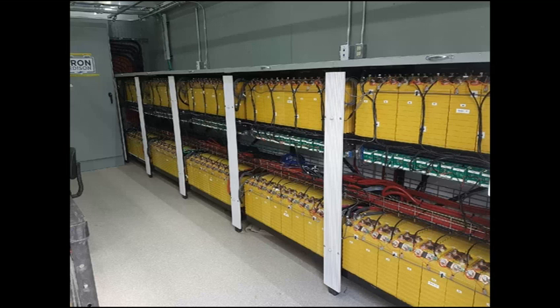And even with a week or two of cloudy weather, there's enough battery energy to keep the system up and running, and they still have those generators on site as a backup in case all else fails. Yeah, this site, it kind of seems disproportional, the size of the battery compared to the two Schneider inverters there. That's because they had 2 weeks of autonomy is what they required in the battery size here. And a lot of the equipment is running DC direct using that positive 52 volts to run the radio telecommunications equipment. Yeah, very neat application.